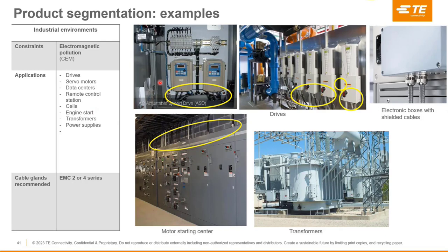Another one here to finish on EMC. EMC usually applies when you have inverters. Inverters are a good source of EMC noise on the line, so most of the time everything is shielded, all the cables. And when you have shielded cable, you also need the shielded cable glands that go with it, to make sure you're not introducing noise inside the cabinet.